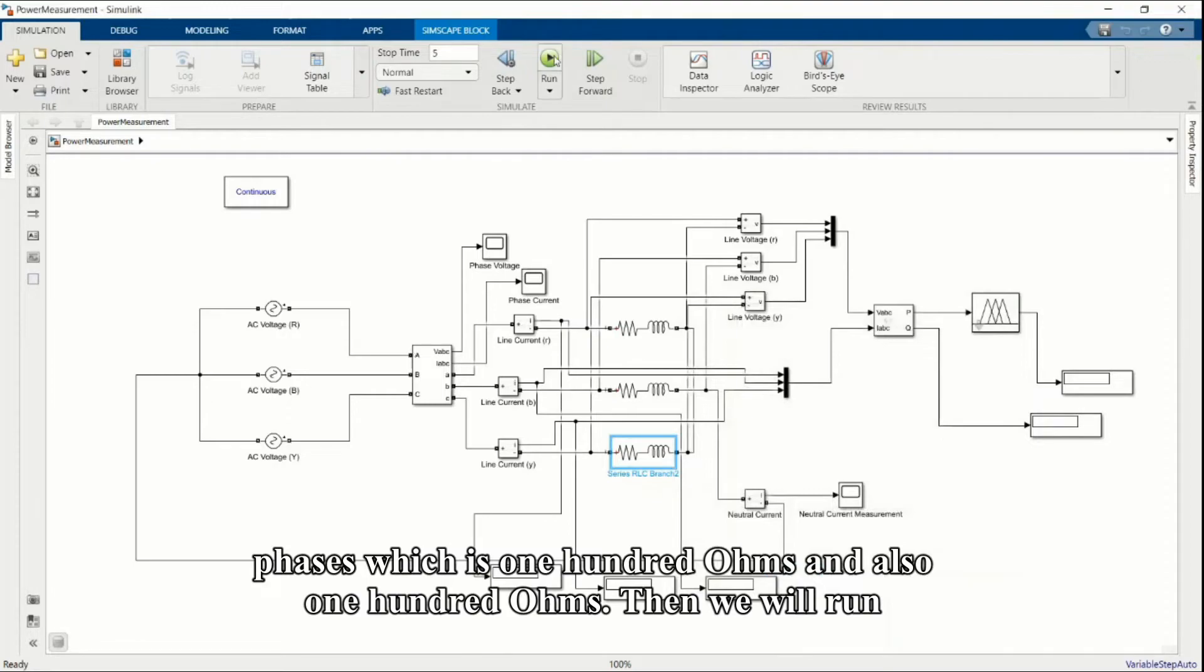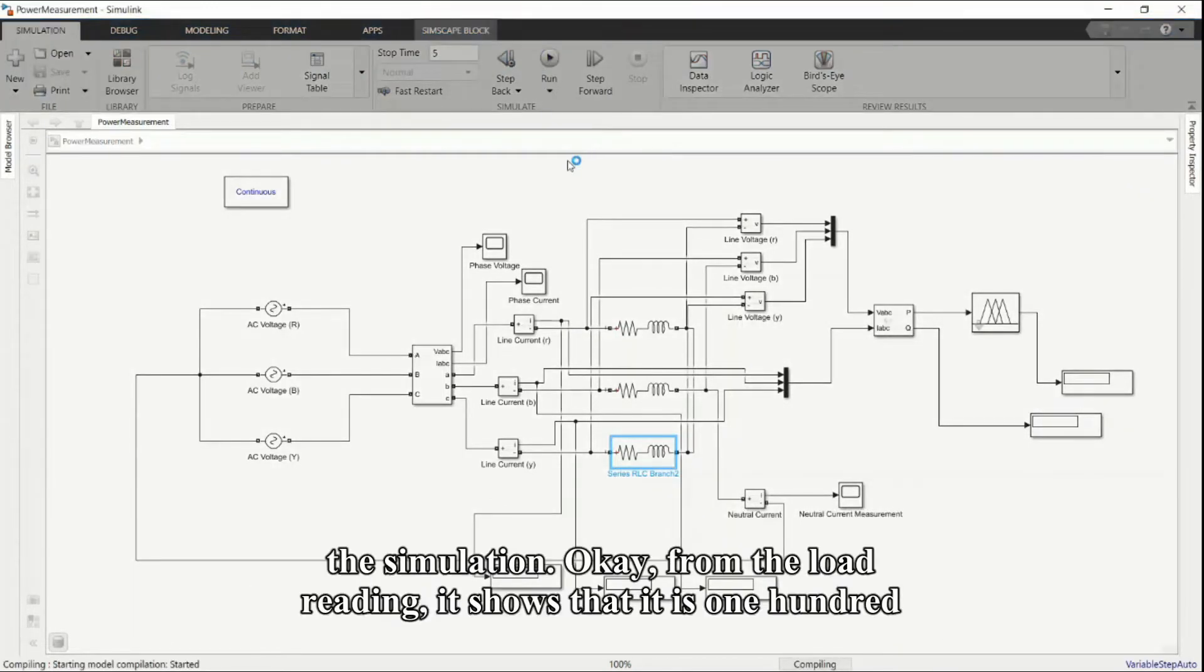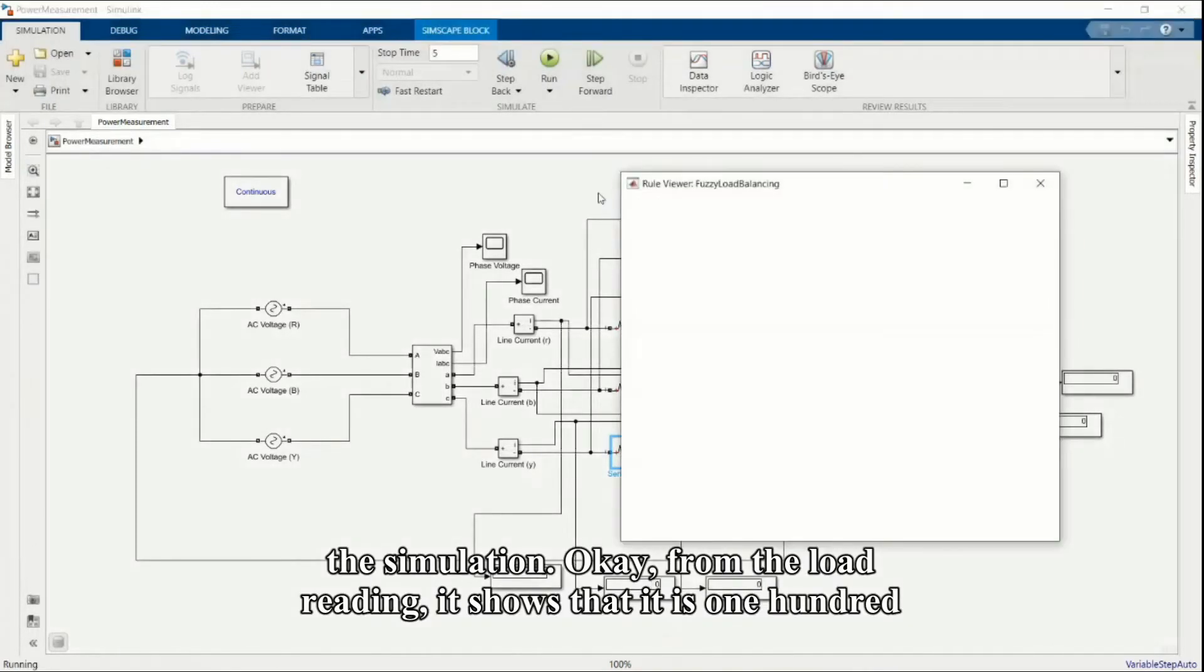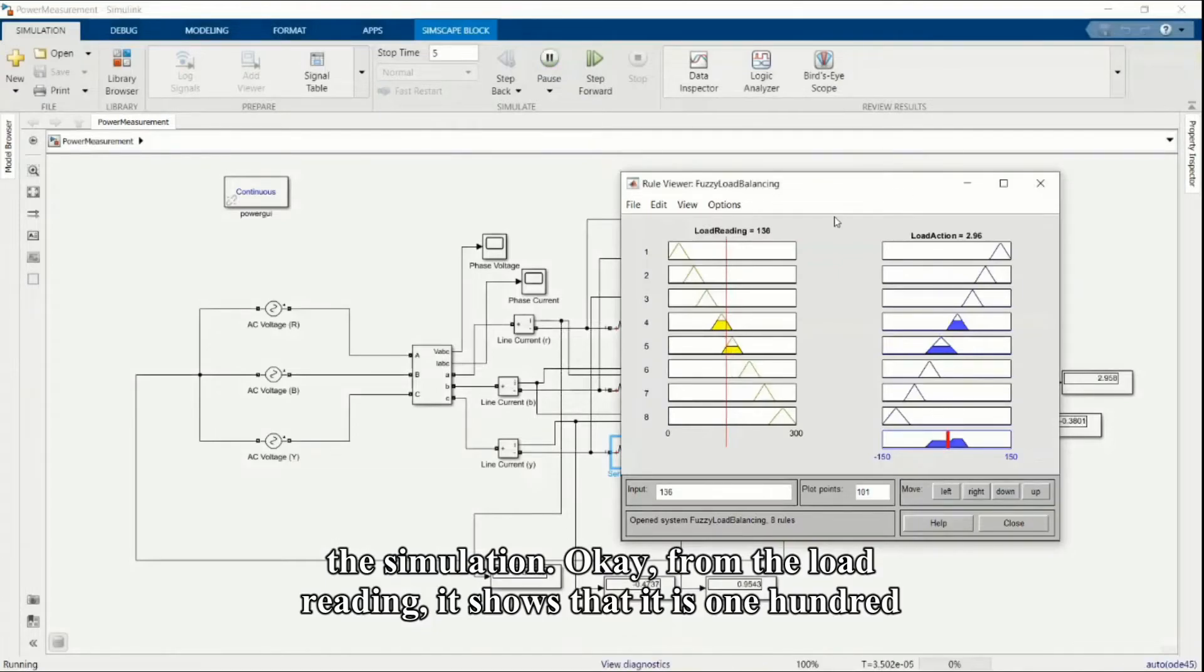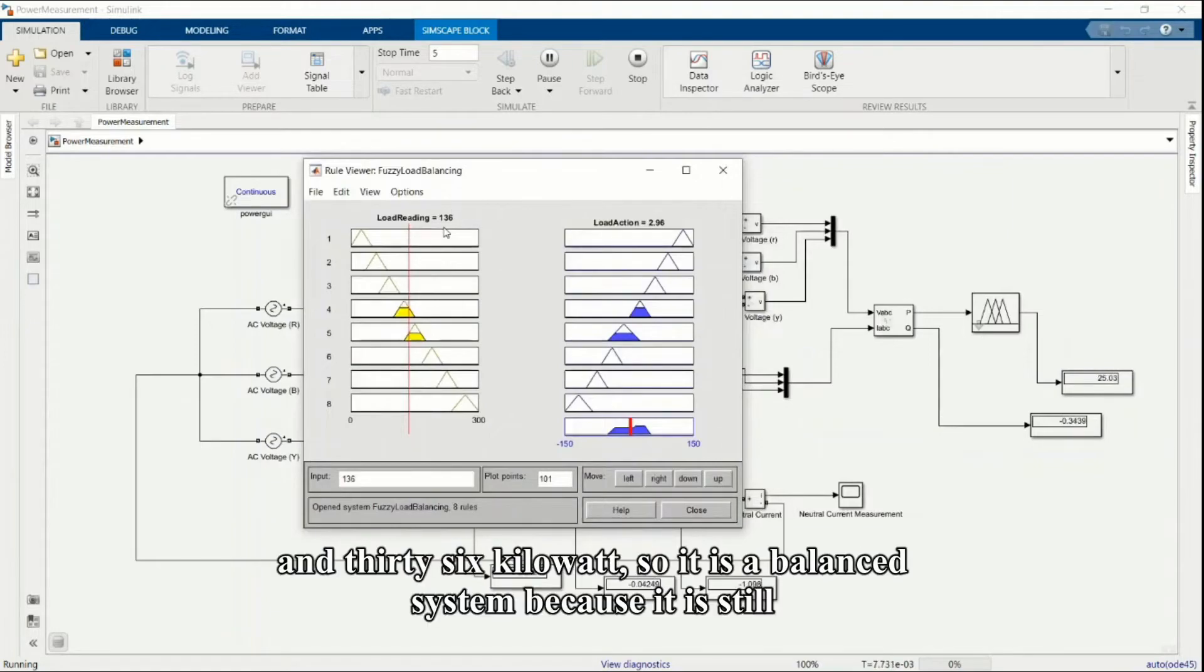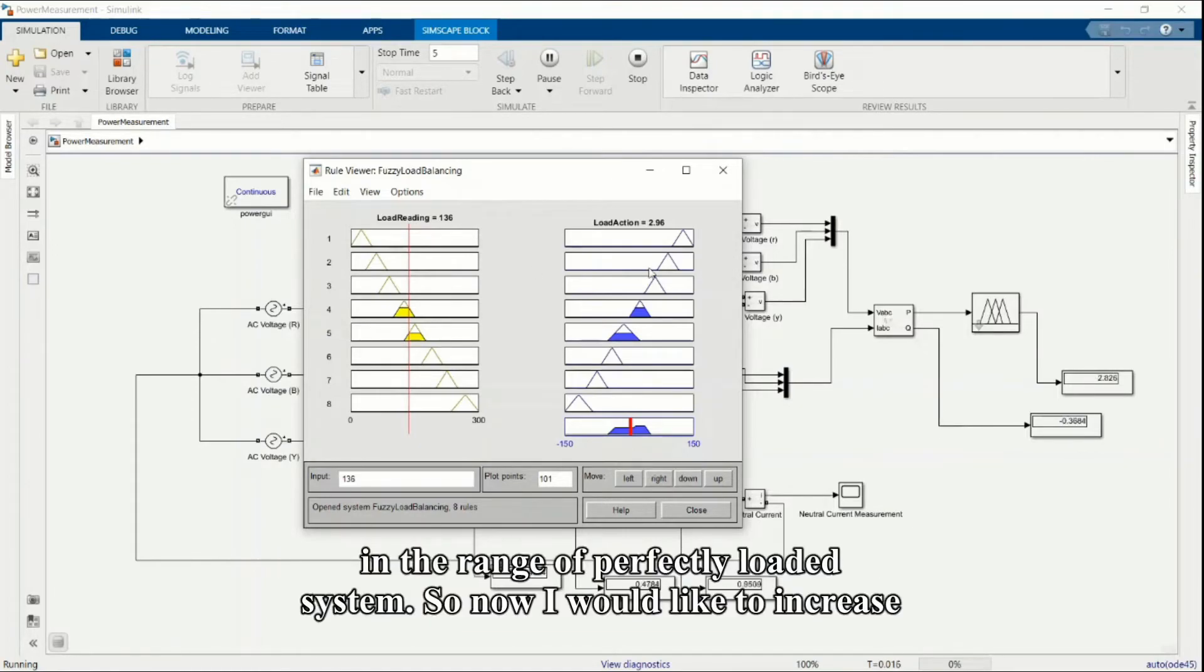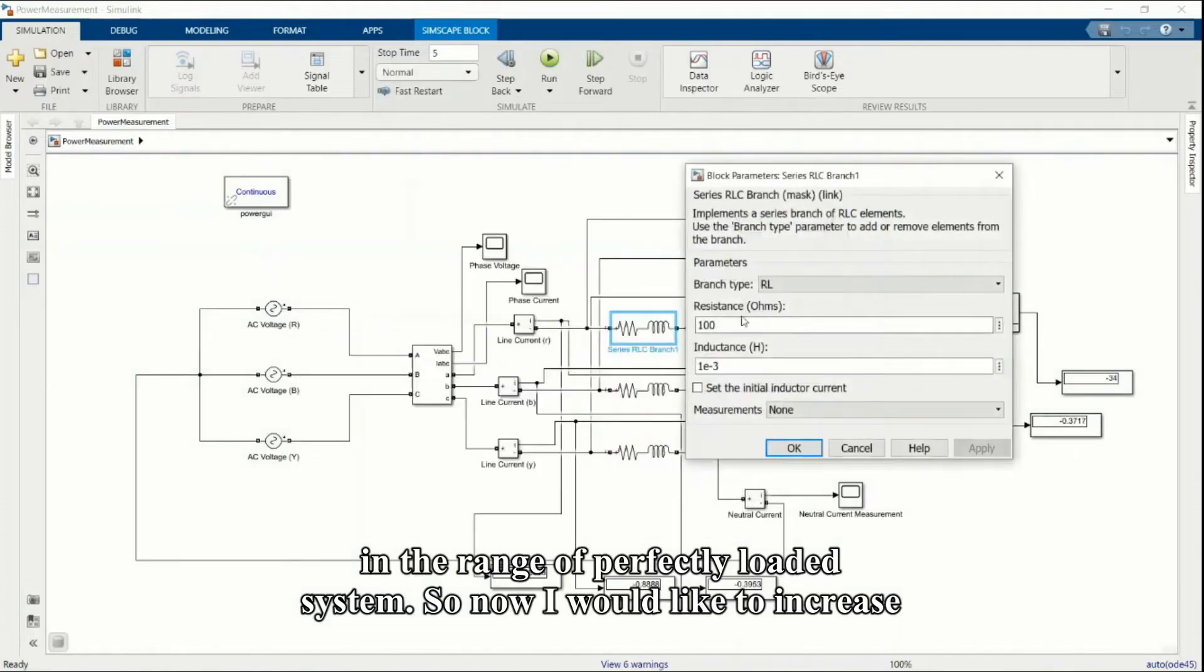Then we will run the simulation. From the load reading it shows that it is 136 kilowatts, so it is a balanced system because it is still in the range of perfectly loaded system.